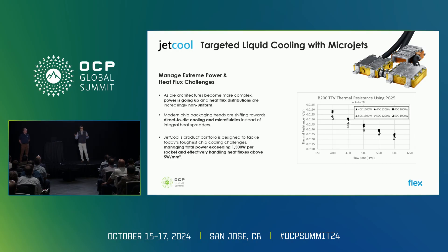It's not just the total power — it's the power density, the heat flux of these devices. With Jetcool's approach, you can get really good performance and cool today's current generation, the next generation, and the generation after that. We're showing GB200 products today with a live demonstration in the Flex booth, where we're getting industry-leading thermal resistances of 0.013 — inclusive of all the TIMs and layers in the cold plate. That's very strong thermal performance, enabling high-power devices and the power densities needed for racks that are no longer 50 kW or 100 kW, but looking toward 200 to 300 kilowatt racks. Not a problem with solutions like Jetcool.